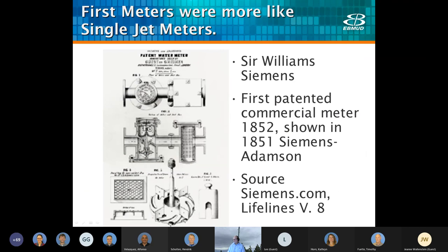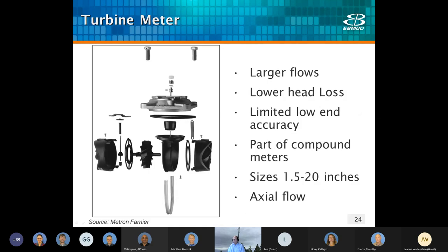Velocity meters such as single jets and turbines have been around a long time in various forms. They grew out of current or stream meters originating in 1790 and credited to Reinhard Woltman in Germany. In the 1850s, one of the first commercial meters was produced by Siemens. Turbine meters are designed for high flow with low head loss, but they're less accurate at lower flows. You might see this meter used on large irrigation sites like golf courses or cemeteries, and they're also used as part of compound meters.